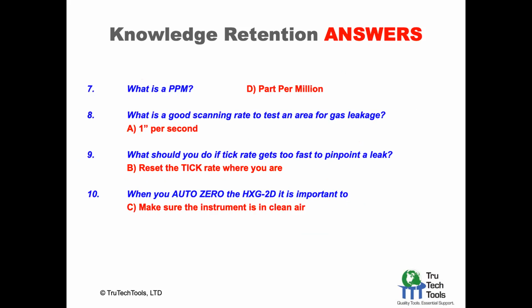ppm is a part per million. I'm sure everybody probably got that one. Then a good scanning rate is about 1 inch per second. Give the meter a chance to react. And if it starts to tick too fast when you're trying to pinpoint a leak, reset the tick rate to where you are, and then auto zero to make sure the instrument's in clean air.